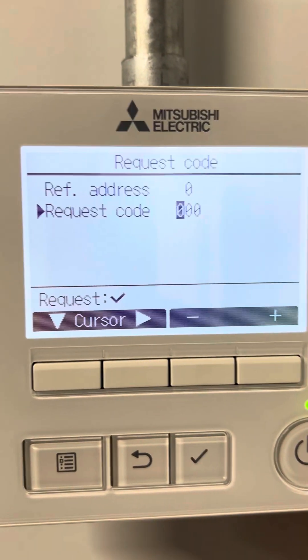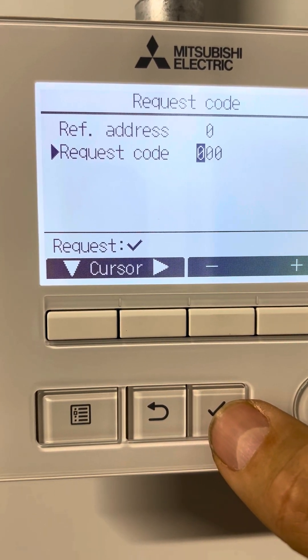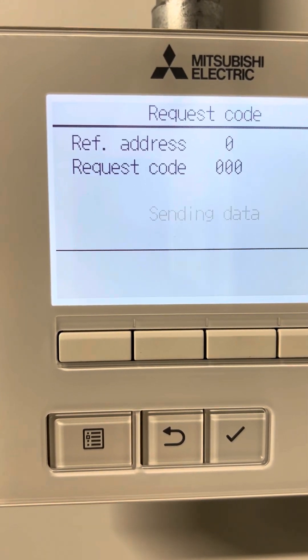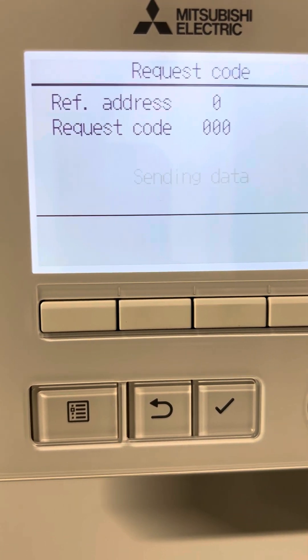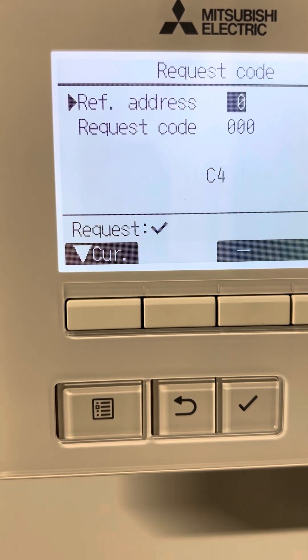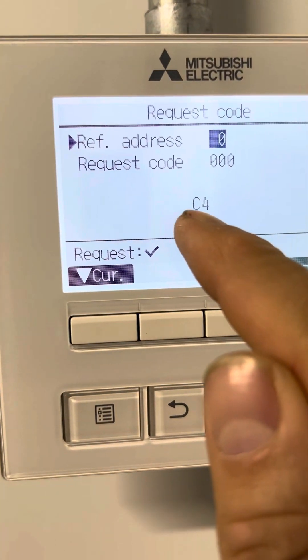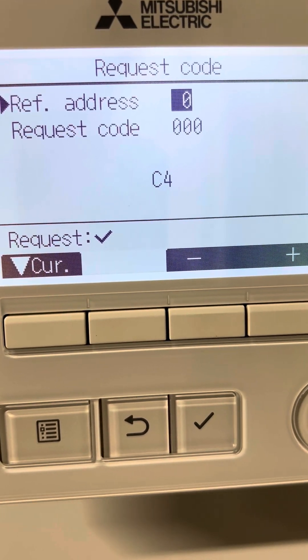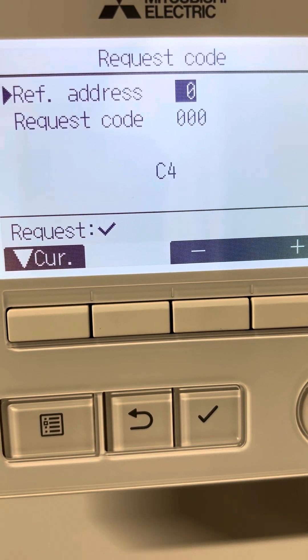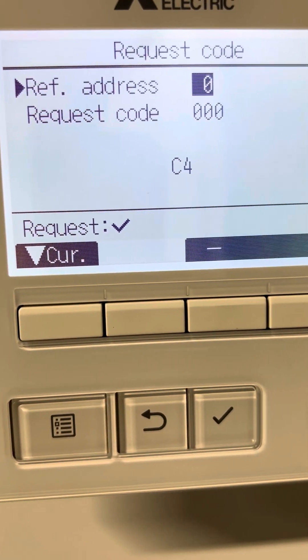Request code zero displays the operation and relay output state. If I send the data I can get the operation state. At the moment it displays C4, so we have a character and a number. Characters could be either 0, C, H, or D for different operation modes like cooling, heating, defrost.